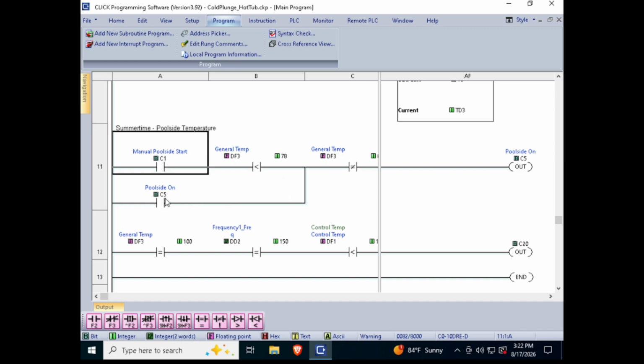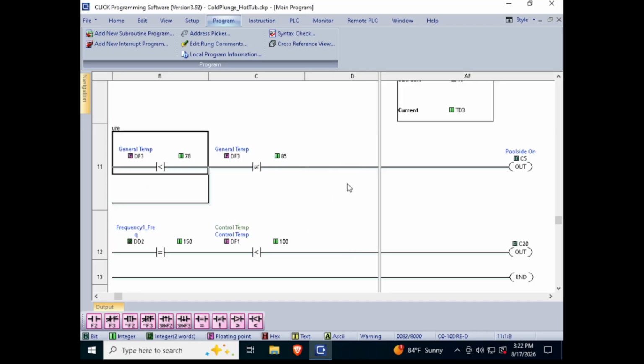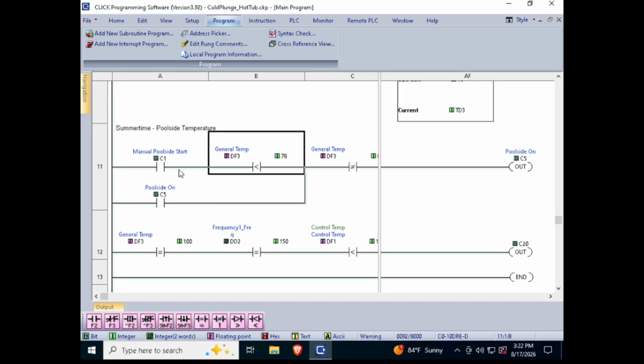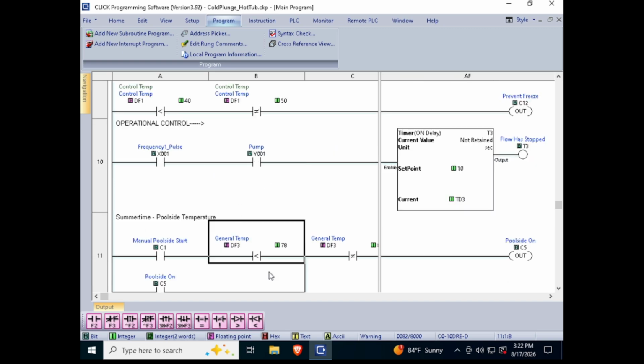This will still be on because we have this manual button as a toggle button. So it'll unlatch this rung down here, which will then only turn the heater back on once it goes below 78 — remember, it's 85 degrees right now. Because then this rung has to be true for the heater to turn back on, and it'll do the whole process again, latching and so on. So it'll always stay between 78 and 85. I found this really helpful so you don't get a lot of flicker from the heater turning on and off repeatedly with just a 2-degree difference — you need a good, a little over 5-degree threshold difference to make this work.